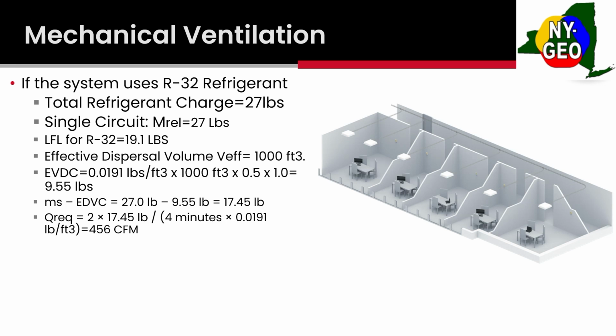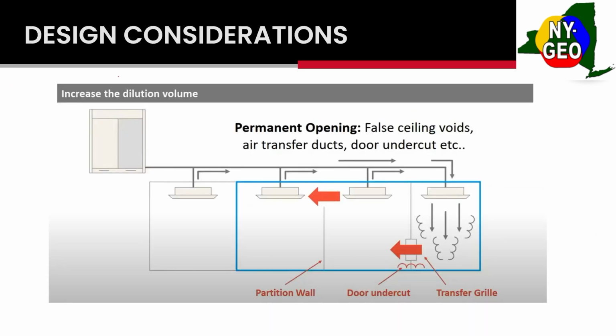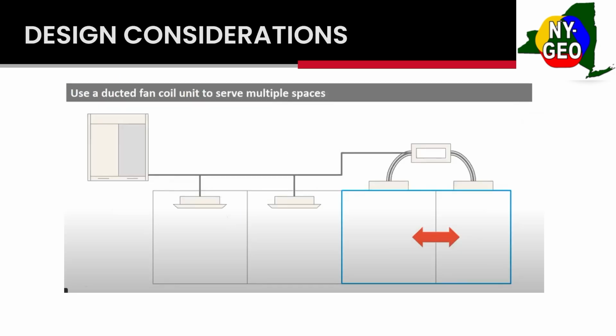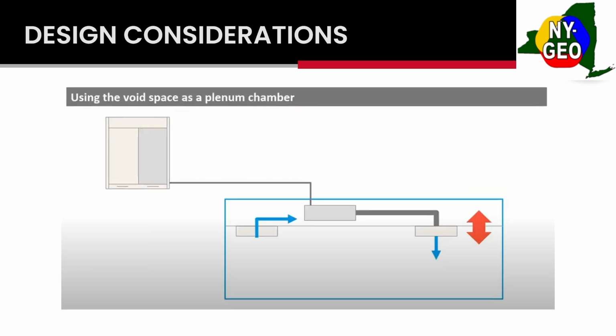Some more design considerations. Talk about these fan coils. You put your door undercut there. This is an older slide. This is from 410A. So this right here is no longer valid because it's too high. It needs to be no higher than 12 inches off the ground. Ducted fan coils, we just talked about that. So each room having its own fan coil, you do a ducted one and duct 2 rooms together. It's a great way to take care of that. And here's another example of using that plenum, because now you can use this entire plenum space in your volume calculations. That helps you meet ASHRAE 15.